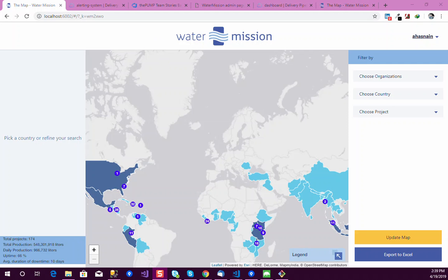So we implemented two more endpoints. One is for the pressure sensor and one is for the other 4-20 mA sensor, and each endpoint uses its own sensor's values. In the other 4-20 mA endpoint we use the low calibration and high calibration which are assigned with the other 4-20 mA sensor.